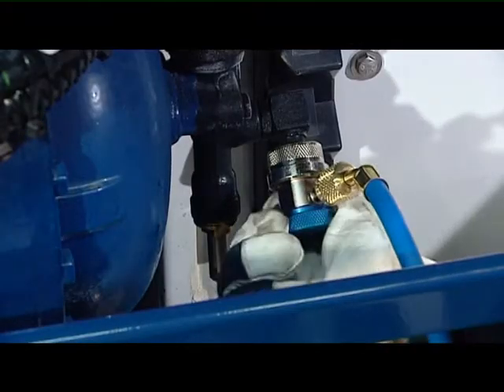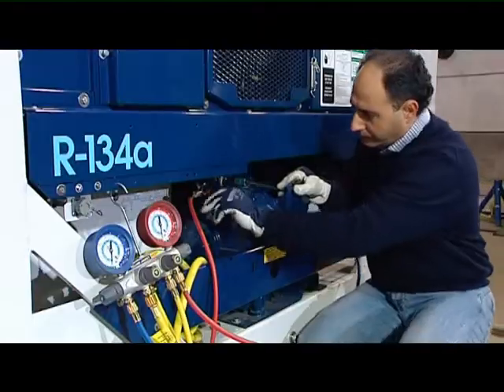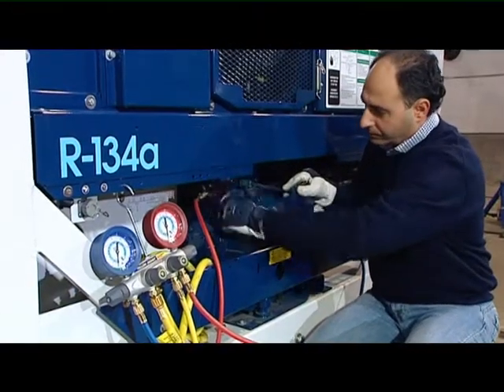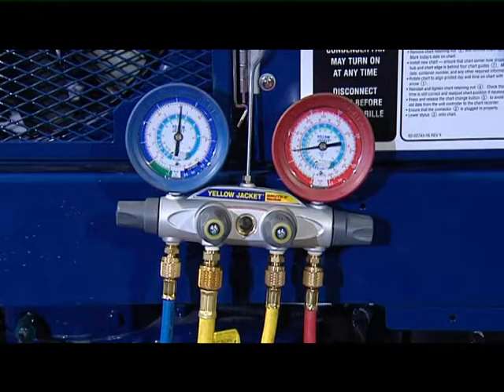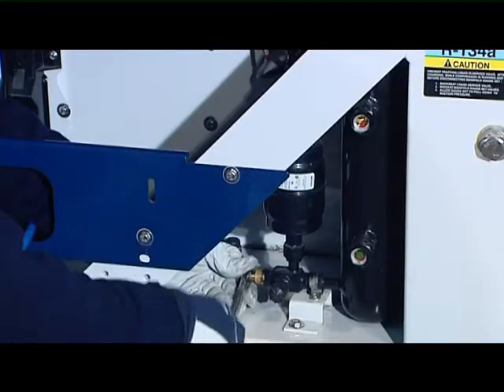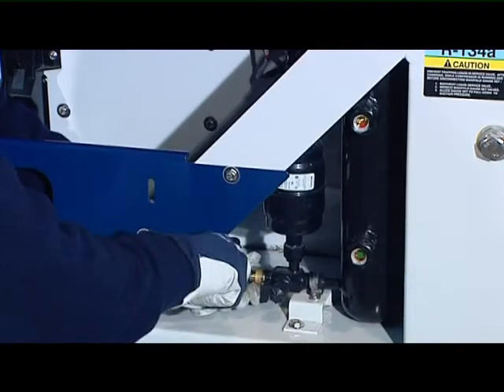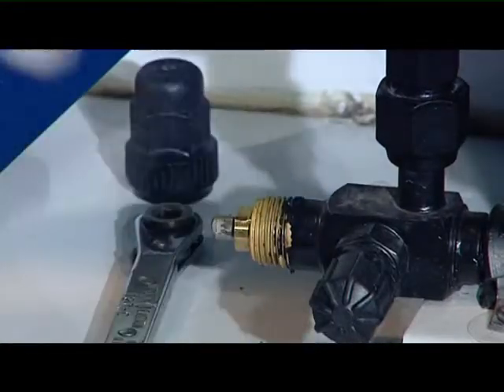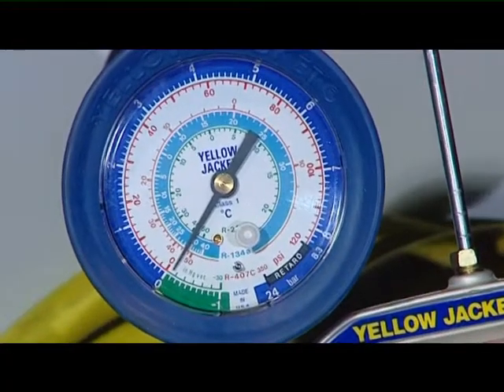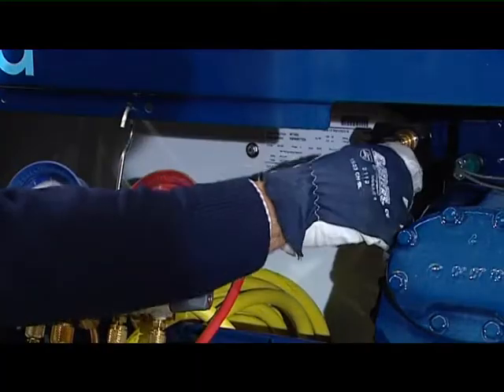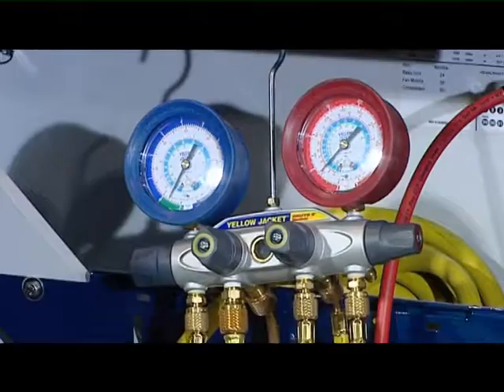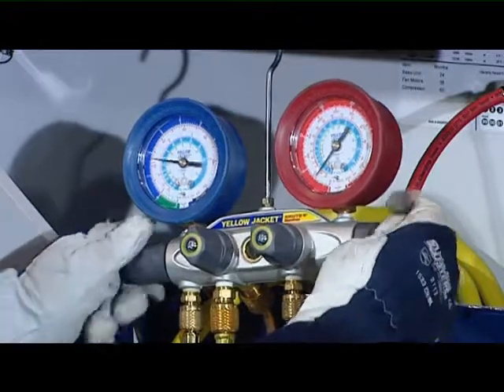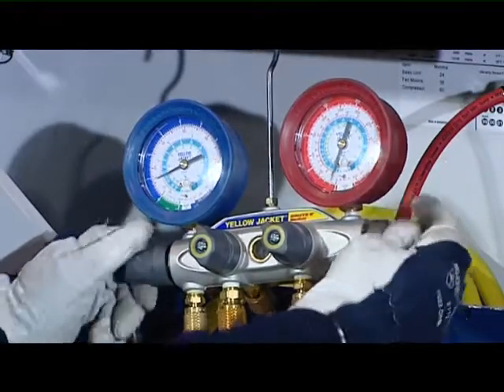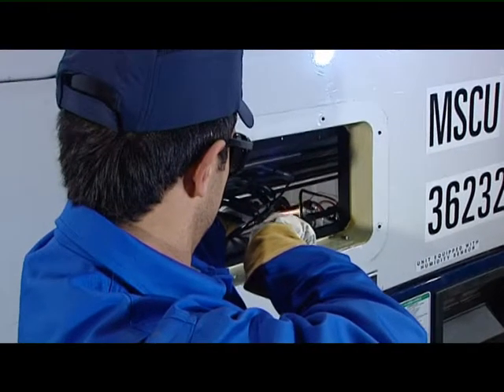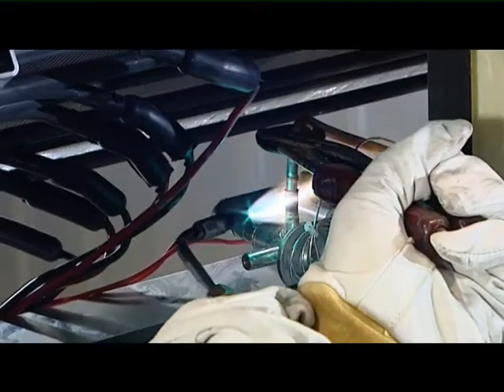To replace the TXV valve, you first have to pump down the unit as follows. Connect the manifold to the compressor's valve and read the pressures. Switch on the unit and place the king valve completely front-seated. When gauge indicates vacuum, switch off the unit and place the discharge valve completely front-seated. Open both hand valves on the manifold. Now you can replace the TXV valve.